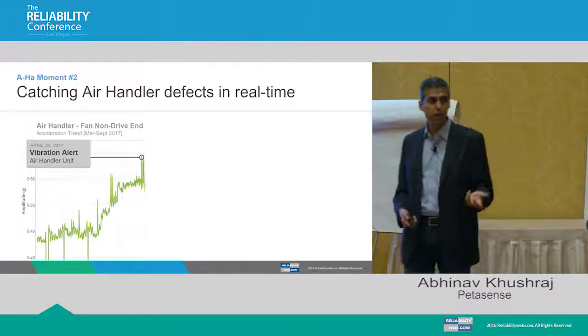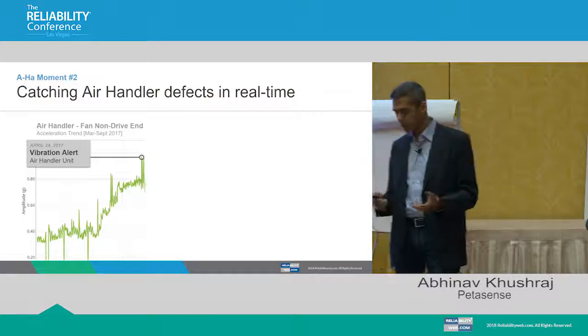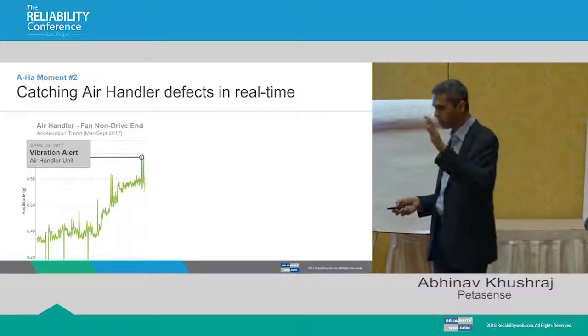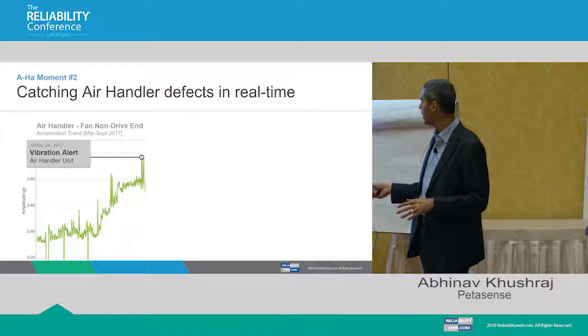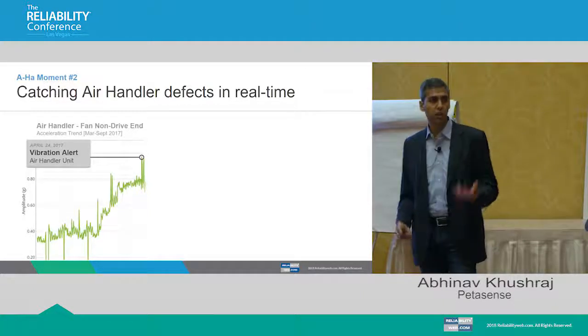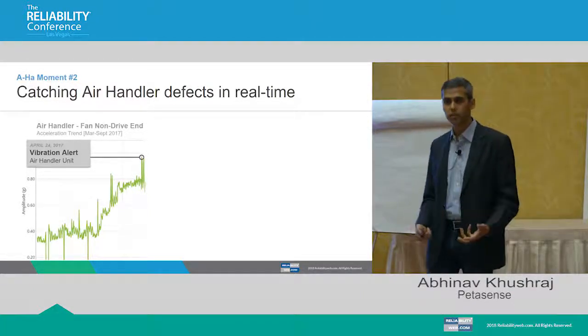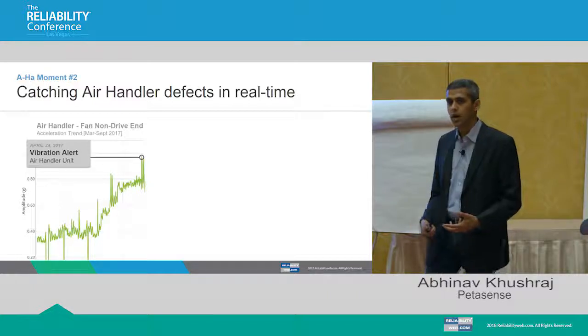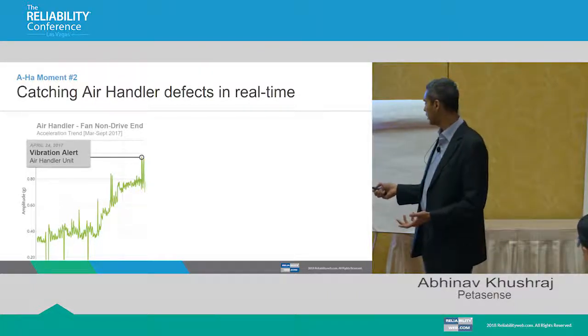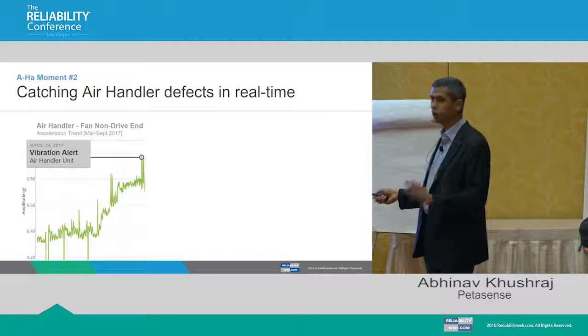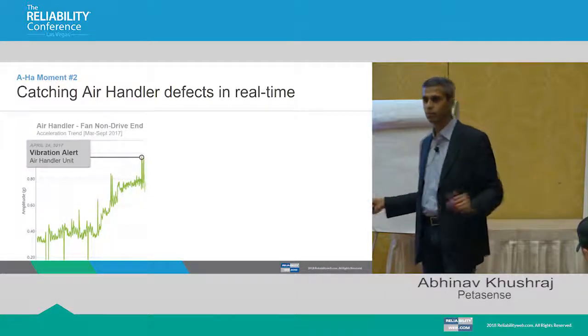The monitoring had begun around March time frame, and the overall vibration started to inch upwards around here. Obviously that's a source of concern when overall vibration goes up. And since you had the real-time data, in this case you knew it was not just an operational thing like the other example we saw previously.